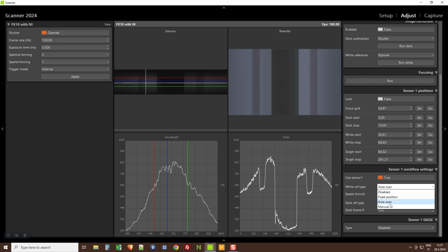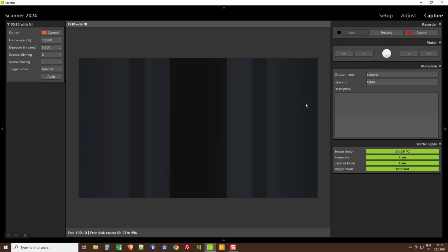Here with the scanner, I prefer to use the area scan because if there is dust on the white reference, when you scan it and you compute the average, or the software computes it for you, these dots will somehow vanish with the averaging. For the white reference, it's always better to keep it clean all the time. If it is dirty, you can use first an air blower, or you can sand it with a sandpaper to remove the dust which is encrusted in it. So once you have done that, you are ready to acquire the data.